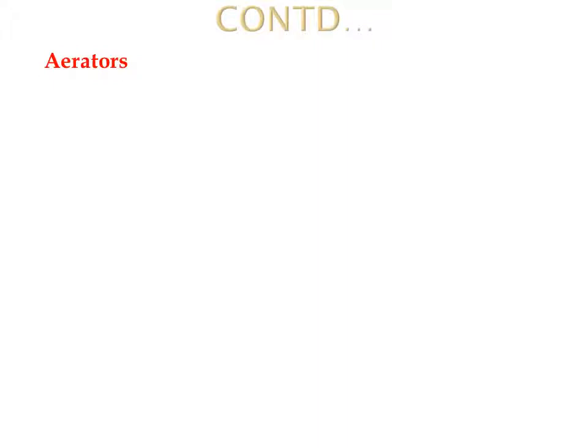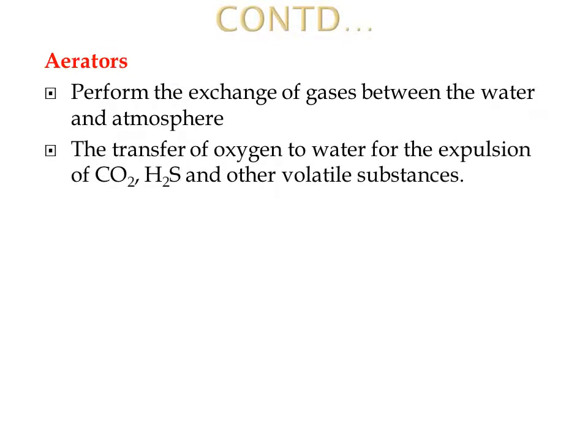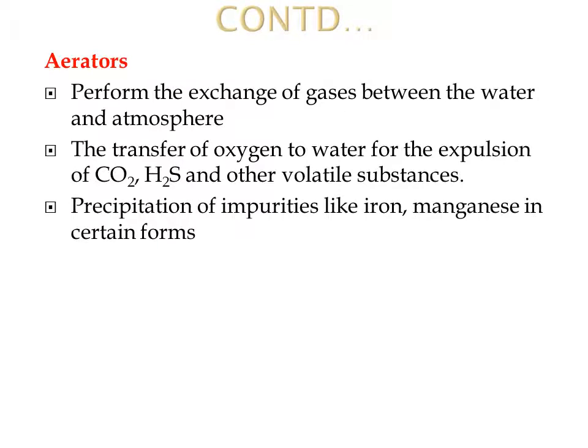Aerators. Aerators perform aeration, which brings water in close contact with air, and thus exchange of gases takes place between water and atmosphere. Oxygen gets dissolved in water and expels the dissolved gases that are present in the wastewater, such as carbon dioxide and hydrogen sulfide, and besides that, volatile chemicals that are present in the industrial wastewater also get expelled.